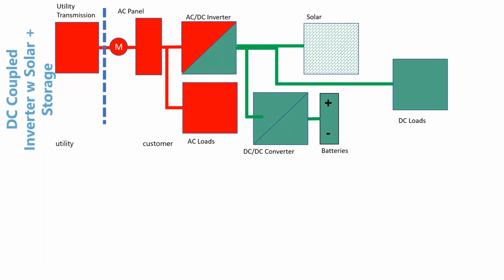In comes what we refer to as a DC coupled hybrid inverter. What this device does is it incorporates a DC feed from the solar, but rather than inverting it to AC to be used or stored, there's a DC side to that equipment. And we can then supply power generated from the solar to batteries and to DC loads off of that one inverter system. So that's how we've organized the house electrical infrastructure for this home in Virginia. And we've identified a number of the electrical loads in the house that can be fed off the DC side of the hybrid inverter.